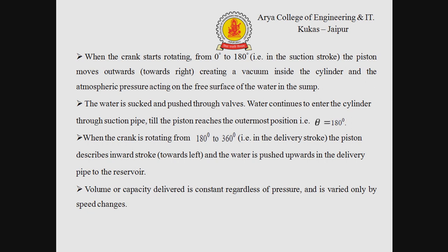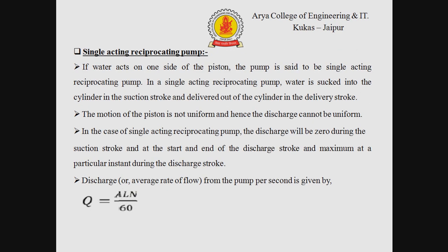When the crank starts rotating from 0 to 180 degrees, the piston moves outwards creating a vacuum inside the cylinder, and the atmospheric pressure acting on the free surface of the water in the sump causes water to be sucked and pushed through the valves. Water continues to enter the cylinder through the suction pipe until the piston reaches the outermost position at theta equals 180 degrees. When the crank rotates from 180 to 360 degrees, the piston describes an inward stroke and the water is pushed upwards through the delivery pipe to the reservoir. Volume delivered is constant regardless of pressure and varies only with speed changes.